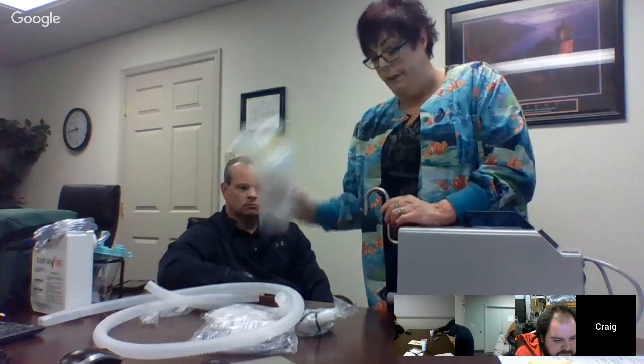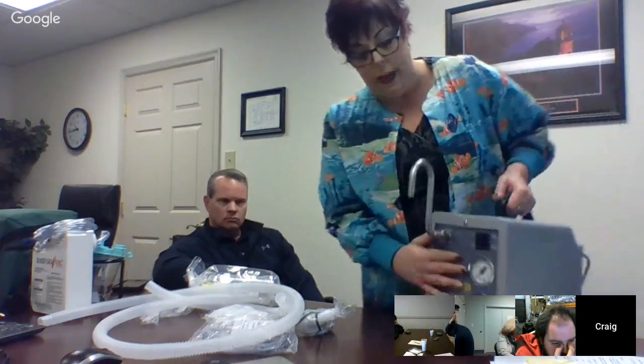And I'm going to plug the machine in. Trip myself. Okay, so now this is the front of the machine. The main thing that you need to know about the front of the machine is how to turn it on and how to turn it off, okay? And this right here is where you're going to put your bottle, your bubble bottle, your large volume nebulizer, okay? But first, before you do that, the technician has to set it. So the way you're going to set this, the PSI you're going to go between is 12 and 15, okay? That's what you want your PSI right here to read.